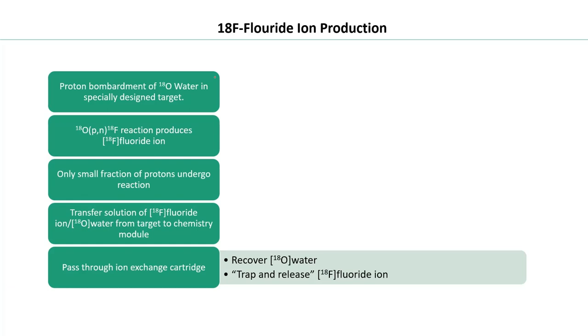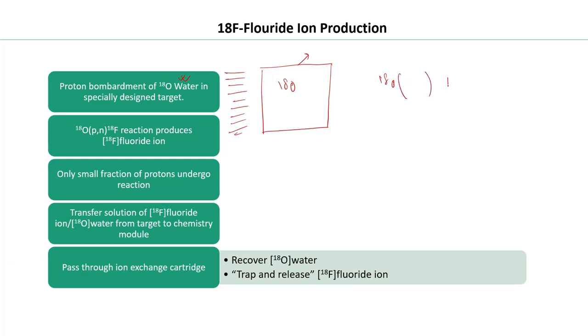For F-18 fluoride ion production, O-18 water is placed inside a specially designed target that contains the water during bombardment. A beam of protons is bombarded onto this target, and as a result, O-18 is converted to F-18 via a p,n nuclear reaction — the oxygen captures a proton, converts to F-18, and emits a high-energy neutron.